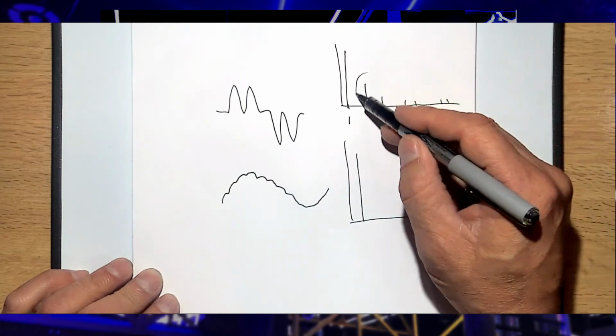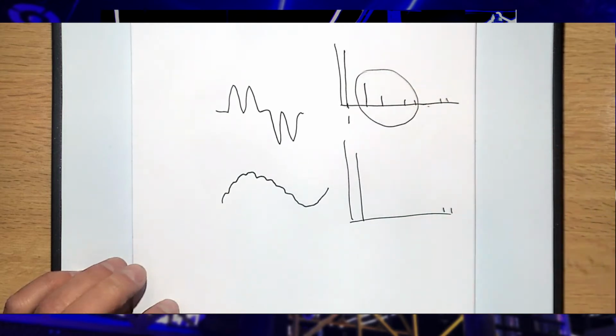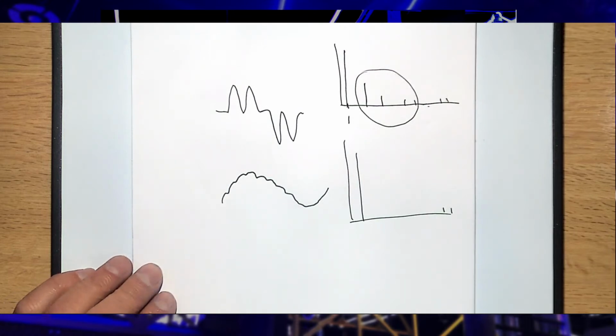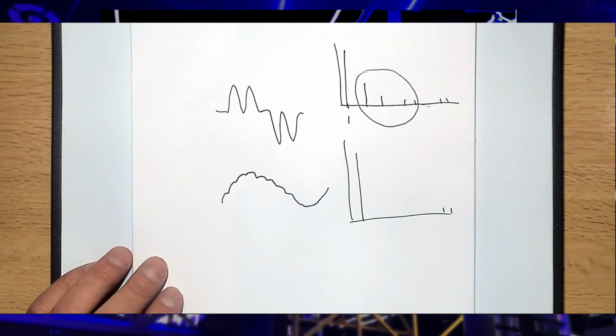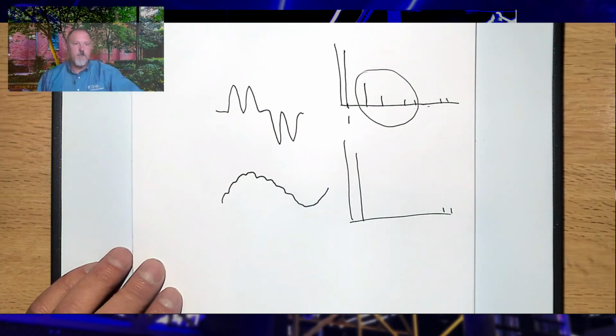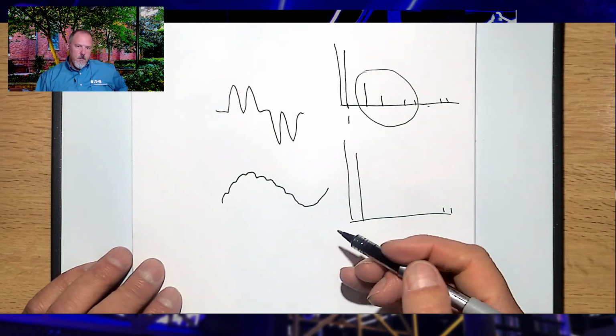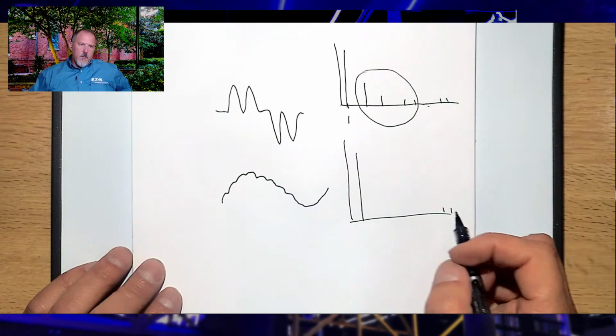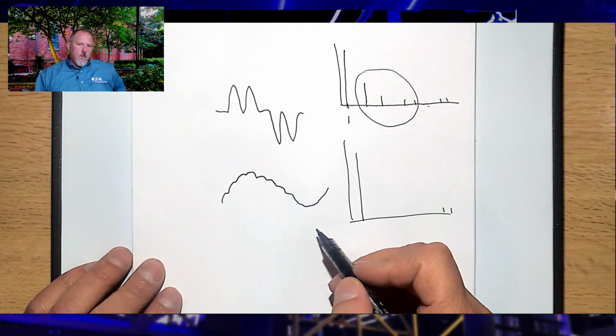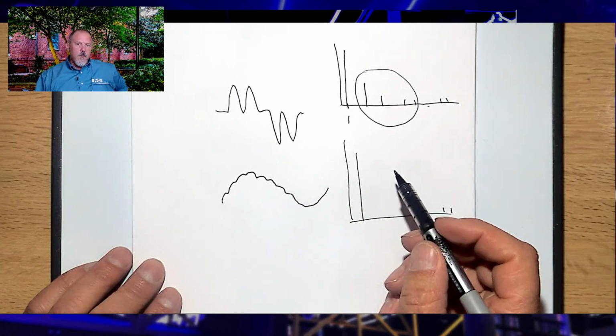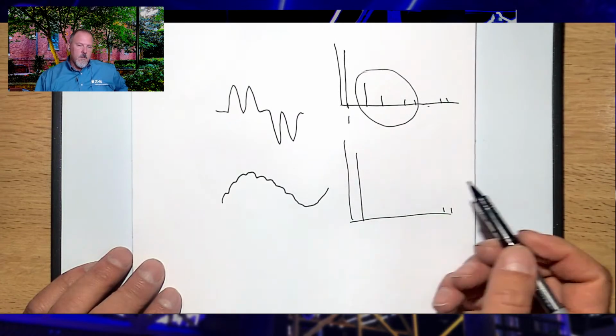So all of these extra harmonics that aren't flowing through the system now, what is that? That's I squared R losses. Going back to our premise that I squared R losses can save you 1 to 2%, it's not a bad thing to eliminate that. So 6 pulse versus 18 pulse, yeah, you can save some. There are going to be a little bit of transformer losses, but at the end of the day, you're at least equal or better with the 18 pulse.